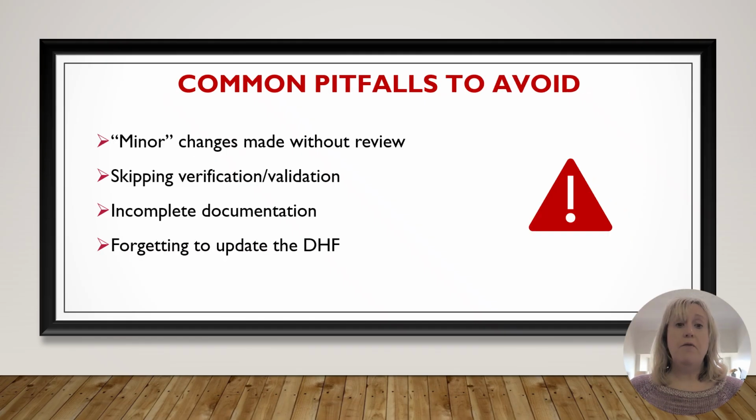Here are some common pitfalls I see during audits and inspections. Teams sometimes make quick fixes without formal review, skip required testing, or forget to update the design history file. Even small changes can have big consequences, so don't cut corners.